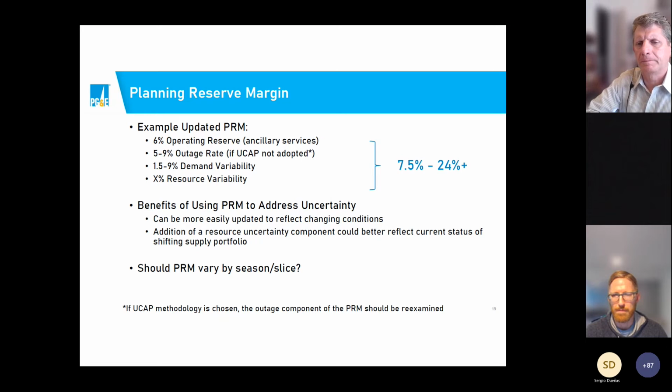And I think the other aspect about the IRP that's going to be pretty useful is that I suspect the PRM that would result in a given fixed level of loss of load expectation is going to depend an awful lot on what the resource mix is. Seems again like a pretty obvious point, but I think that would suggest lodging that within the IRP space, where those considerations of what the generation mix is are expressly being done, that would make a whole lot of sense as well. So I think we may have shocking agreement on this point.